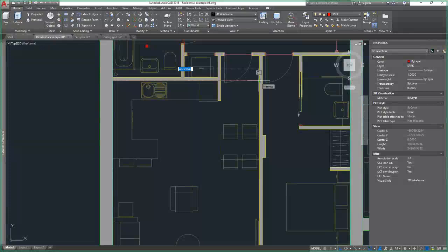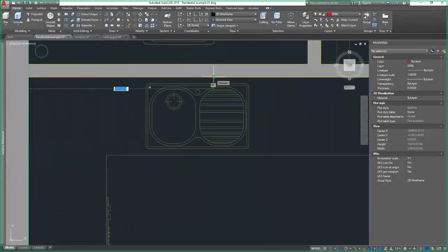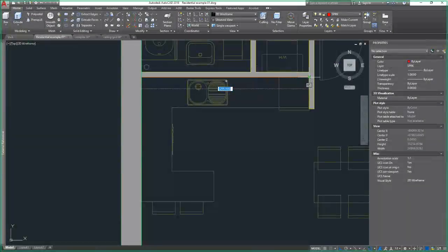So of course I've got 4.6. Ordinarily, following the previous method, I would do 4.6 divided by 2, and that would give me my spacing. But my spacing comes out then at 2.3. 2.3 is too close, okay? 'Cause I need at least 2.4 meters between my sprinkler heads. So in this instance I would do 4.6 minus 2.4, and that would leave me with 2.2. 2.2 divided by 2 is 1.1. So my sprinkler heads are going to be 1.1 meters away from the wall.